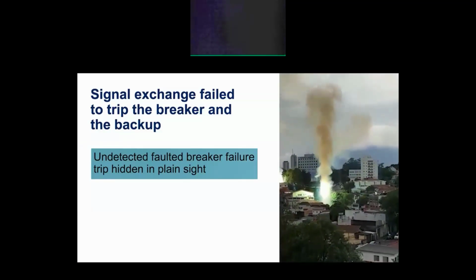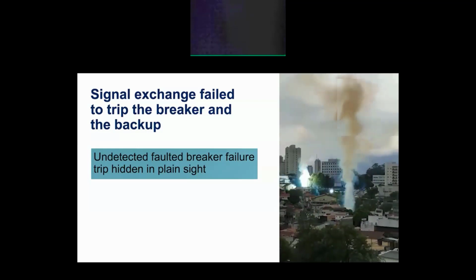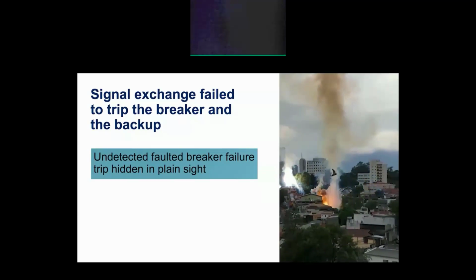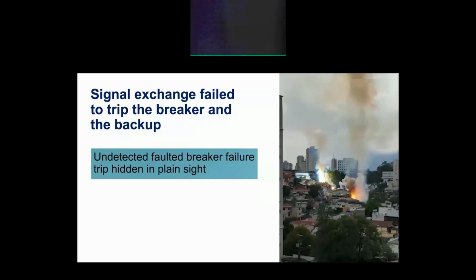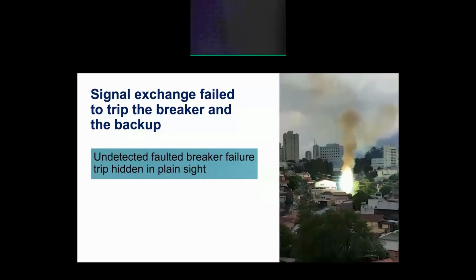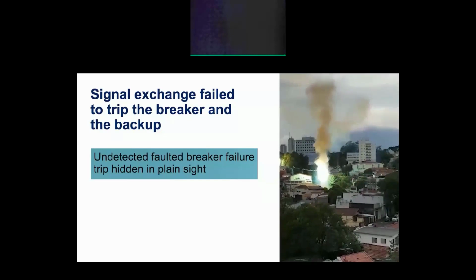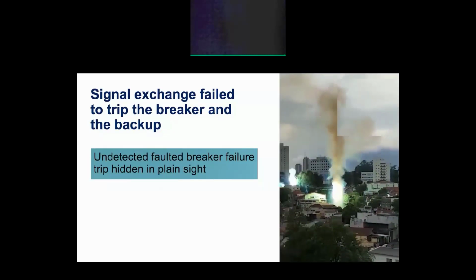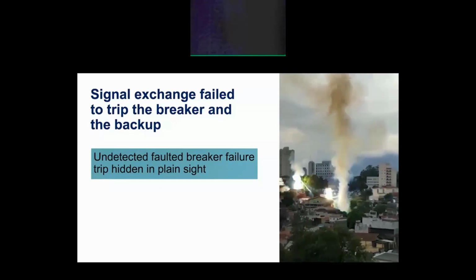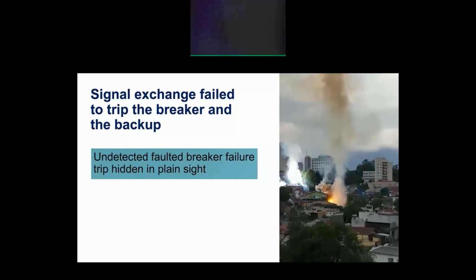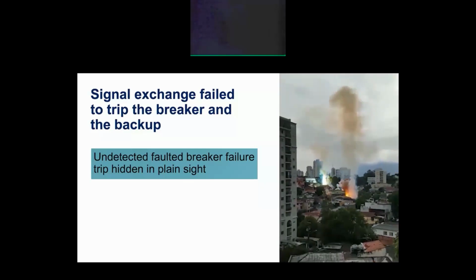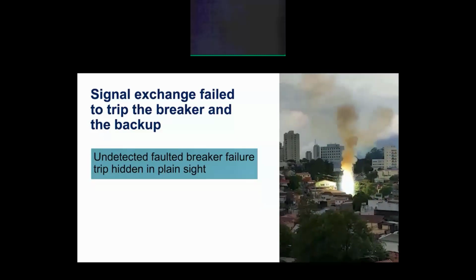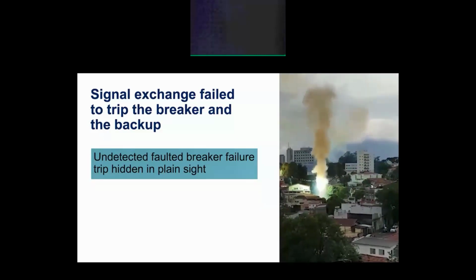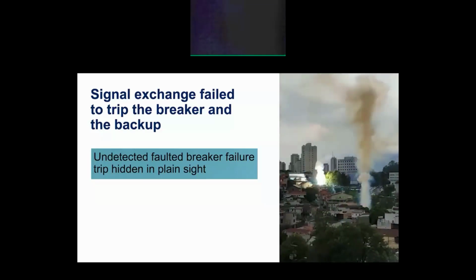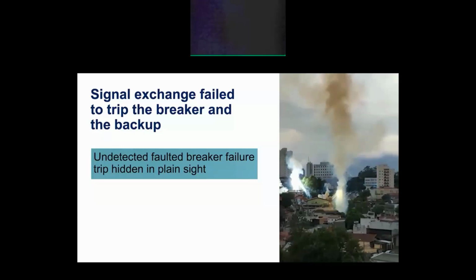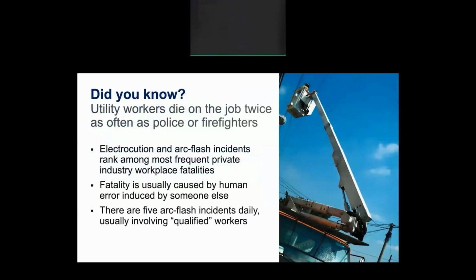As another example, consider this 345 kV fault that happened in Brazil recently. It also took out an 88 kV line below it, and people could have been seriously hurt. Thank goodness no one was hurt, but it did cause a lot of damage and lost business. This illustrates what happens when a trip circuit fails. So this was a conventional trip circuit, but its failure created a fault duration of an astounding 113 seconds, and the outage time was 376 minutes. But the 177 megawatts of interrupted energy was only considered Category 1 severity. Now, clearly, this was much more dangerous and expensive than the interrupted energy metric would indicate.